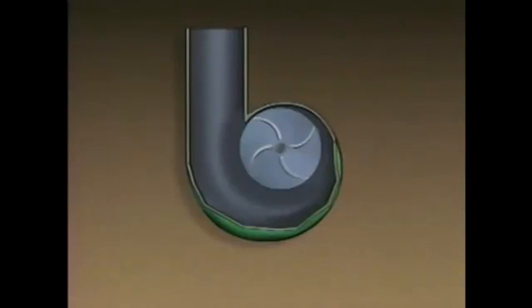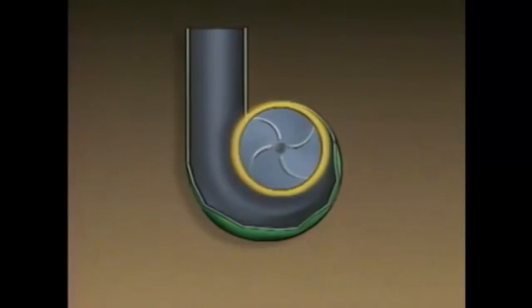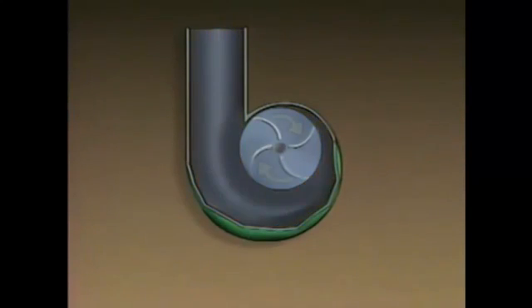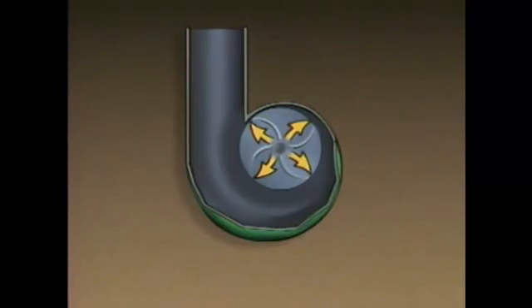We can use a simplified illustration of a centrifugal compressor to see how it works. The compressor's main internal components are an impeller and a volute. The volute is a continually widening chamber that is connected to a gas discharge line. The impeller rotates during operation. Gas that enters the compressor at the center of the impeller is swept up by vanes on the impeller and moved outward by centrifugal force.